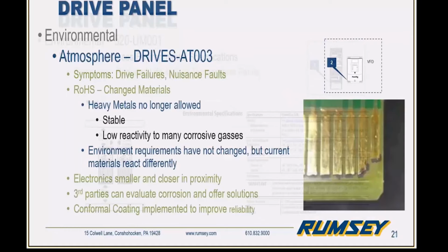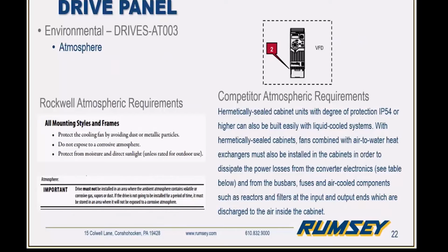Another consideration for the panel is the environment or atmosphere in which the drive is installed. We want to make sure we're not exposing the drive to a lot of dust or corrosive gases, and that we take all the proper considerations to make certain the drive is protected against the environment it's installed in. One of the things that adds reliability is that Rockwell makes sure all of the boards on the PowerFlex drives are conformally coated.